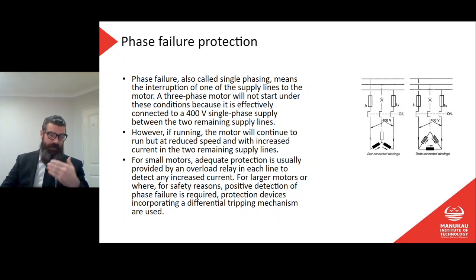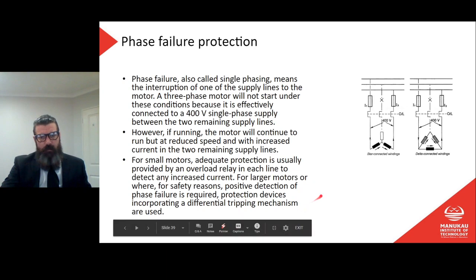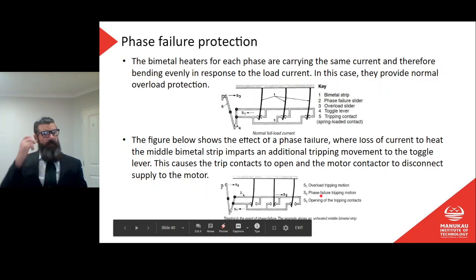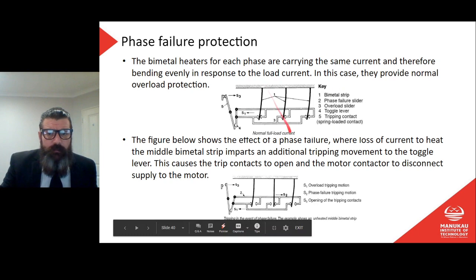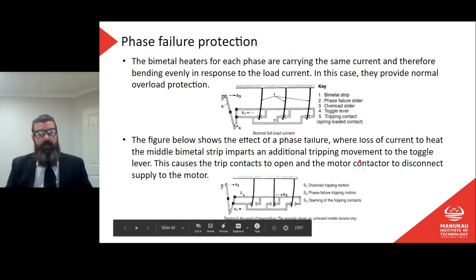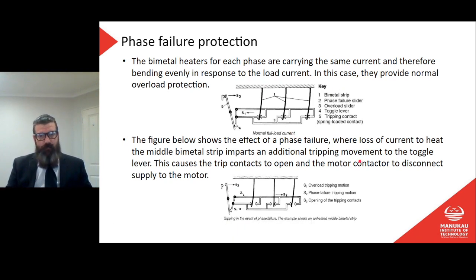As it says there, for safety reasons or for other reasons, we need to have some sort of positive detection, so specifically when that phase is dropped out, we need to know, rather than just relying on overcurrent. Then you'll have a differential tripping mechanism, which we don't need to go into here. And what do we have there? The bimetal heaters for each phase are carrying the same current and therefore bending evenly in response to the load current. In this case, they provide normal overload protection.